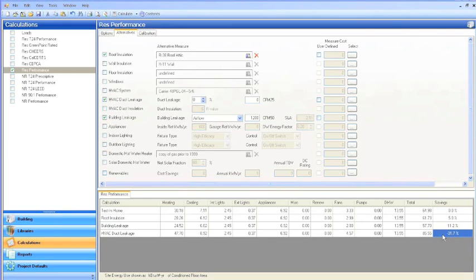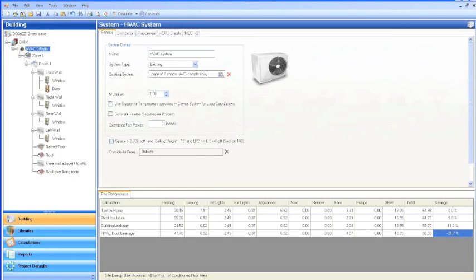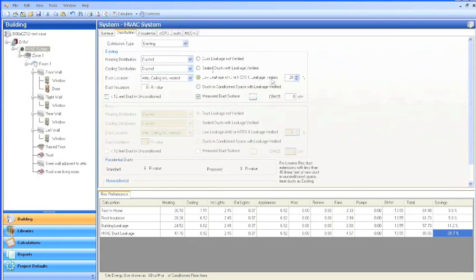If you see something unusual showing up, like a negative savings, which is a terrible thing to have when you've done all this great work on your house, take a look and see what happened in terms of your entries. Maybe something was entered incorrectly. We look up here, and the duct leakage column went to 0. So for some reason I didn't properly make it go to 6 the way that I wanted. So let's compare to make sure that the duct leakage was appropriately entered up above. Duct leakage is under the HVAC system. Here it's 28, so that should be fine.